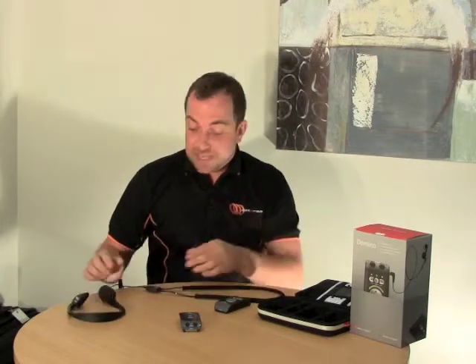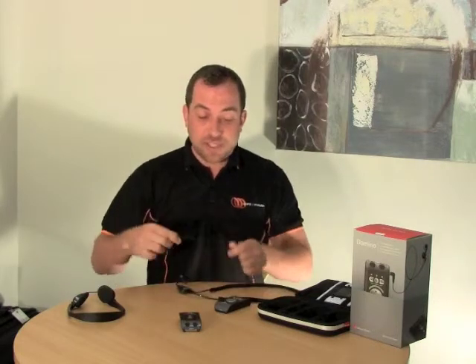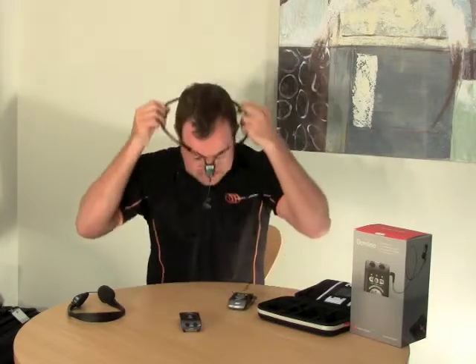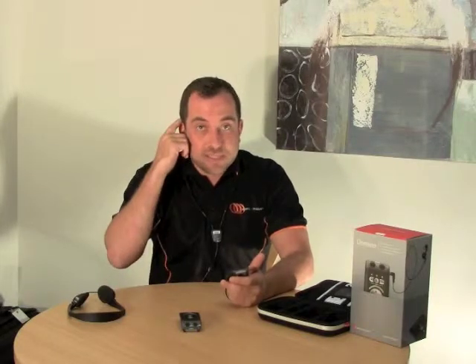For the purpose of today's quick demo, I'm going to show you just using it with the neck loop. So we plug the neck loop into the receiver. We simply wear this neck loop around our neck, and when we're wearing hearing aids, we switch them over to that telecoil program. What that means is that we are reducing the microphone sensitivity here, and we're hearing more from our wireless device. That's the key advantage we have when using an FM system, because hearing aids or even some speech processors or cochlear implants, we find that with the microphone by itself, they're good, but they have a lot of trouble managing in noise, particularly when you want to listen to one person in a room that's full of people who are talking at the same time. So an FM system like this is going to help you overcome a lot of those problems.